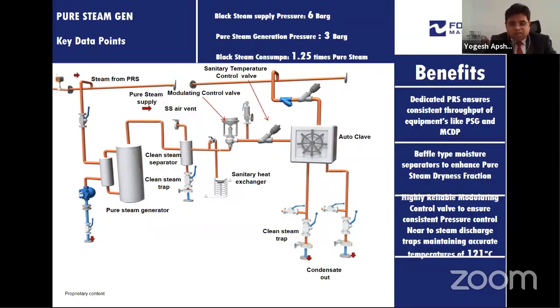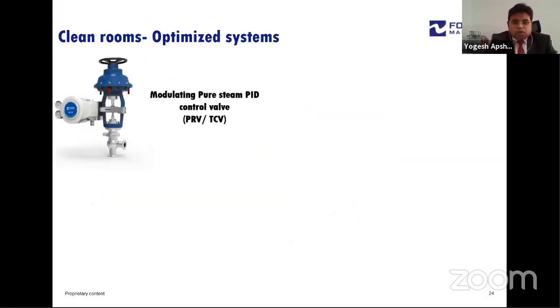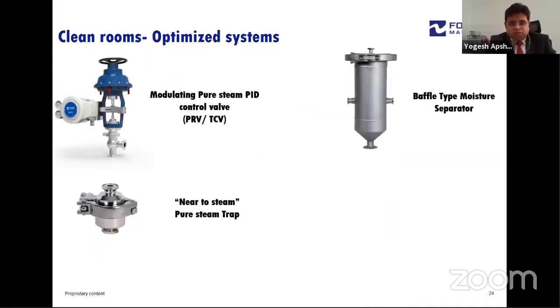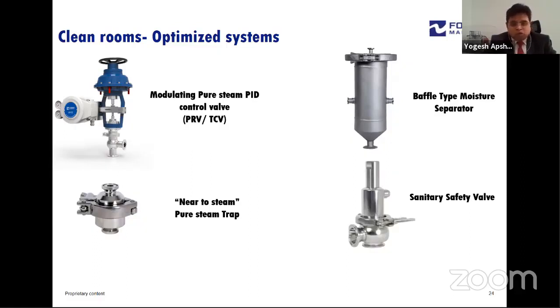In most places, the pure steam condensate is drained to the atmosphere or into the centralized water system, but we can recover this pure steam condensate back to the feeder tank as well. So these are the typical applications and benefits of a pure steam generator, and the intelligent steam systems in pure steam as well as black steam systems. These are the product ranges which we manufacture: pure steam steam traps, pure steam PRVs, modulating control valves, baffle type moisture separators, and sanitary safety valves, all manufactured as per ASME BPE standards.